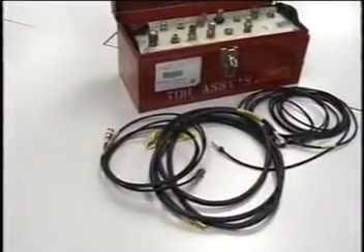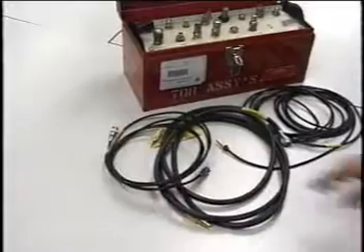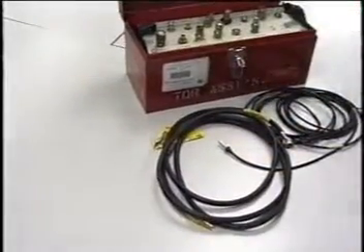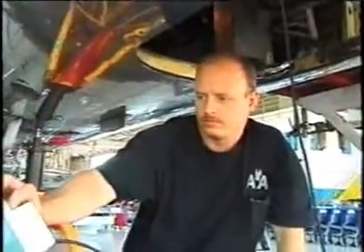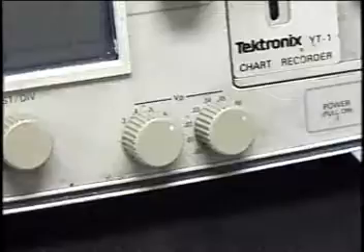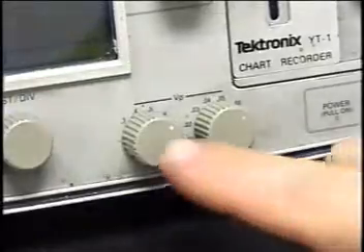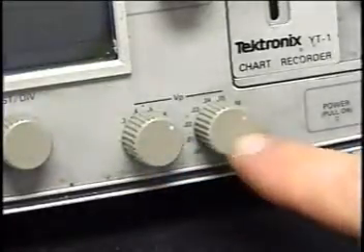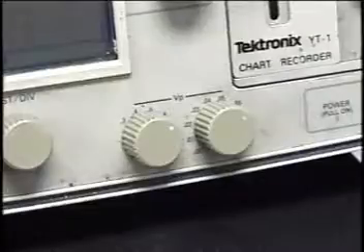You can find the VP of a cable by connecting a known length of the exact type cable to the TDR and adjusting the VP knobs until the end reflection matches the known length. You can then read the VP directly off the VP knobs. Most coax cables on AA aircraft have an impedance of 50 ohms and a VP of 0.66 or 0.78.